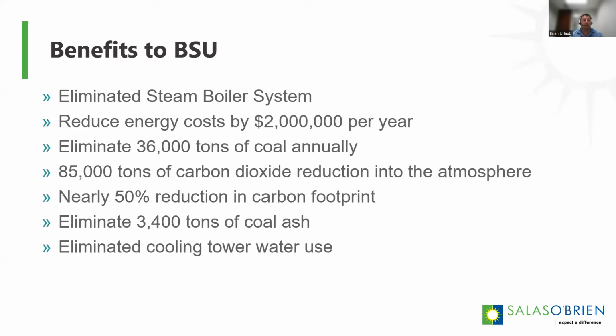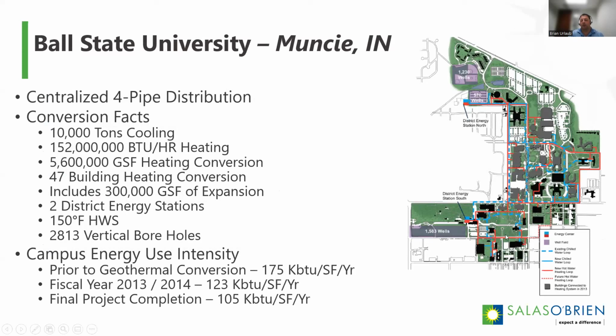annually, 3,400 tons of coal ash. All their cooling towers and water use and chemical treatment from the cooling towers are gone. So a ton of benefits to these district systems. But if you were going to go into a campus like this and do one building at a time, first of all, it would take you decades to do that. Second of all, you don't have enough green space to put loop fields everywhere. And the third thing with these district systems is you get all the diversity of this interconnected system of the student body moving around throughout the day, which is a huge factor in the overall size of the system because you're not sizing for every building peak. And that's really critical to these district systems.